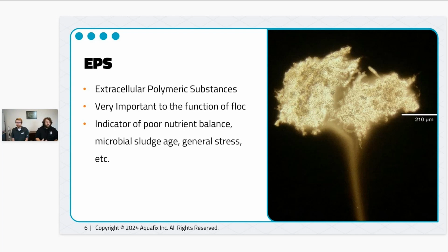Or in the worst case scenario, if you have really big floc, they might have a dynamic sort of population of bacteria where you have anaerobic bacteria existing within the insides of very large mature floc, and those sorts of floc might be shedding ammonia or shedding some other things that we don't really want to see, volatile acids, stuff like that. And you would hope that the edge of the floc would take up some of that stuff from the inside, but sometimes that's not the case depending on other factors that are happening in the plant.